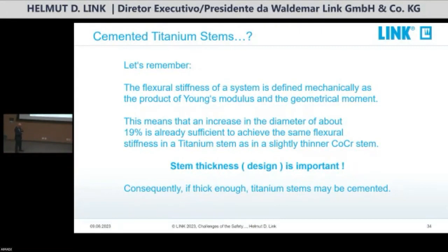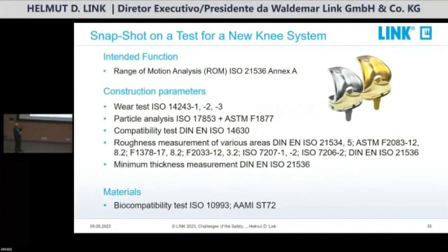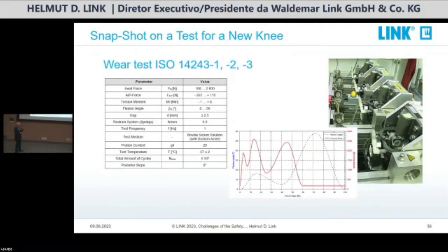Now, what do we do when we produce a new knee system? We do range of motion analysis, wear test, particle analysis, compatibility test, roughness measurement, minimum thickness measurement, and of course, biocompatibility. Here, a view how these tests are done. There are not only 1 or 2 or 3 machines. No, 6 pieces have to be tested to give a statistically acceptable answer.